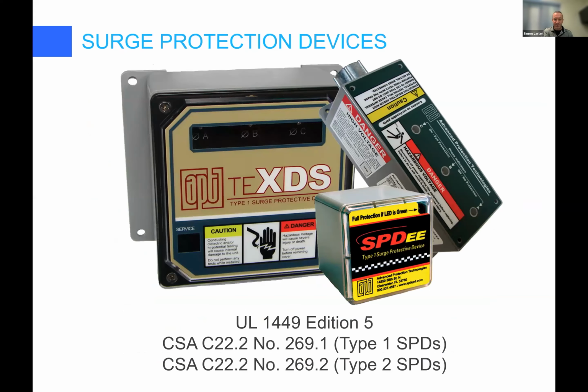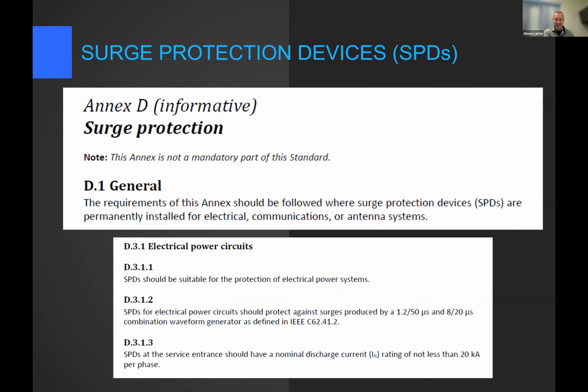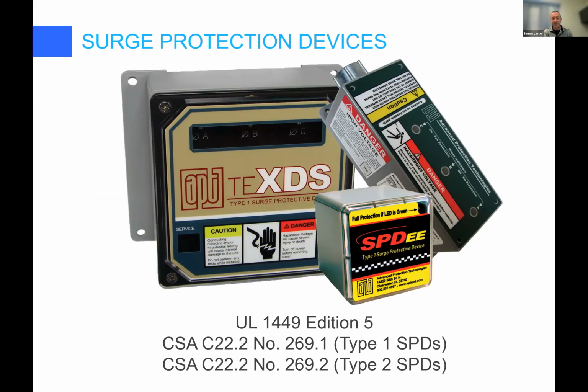The thing to know about surge protection is that they are listed for lightning protection purposes. You can have surge protection devices for switching transients and for power line fluctuations and things like that. But a lightning protection surge device is something different. They are tested against specific surge waveforms, 20 kiloamps for a main electrical surge protective device is the current they test against. So those are tested at the factory against a lightning waveform, 20 kiloamps per phase of discharge current. That's how they're tested, and so they are listed specifically for lightning protection purposes.